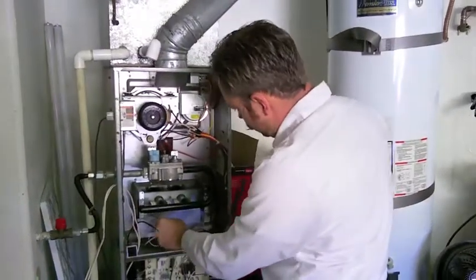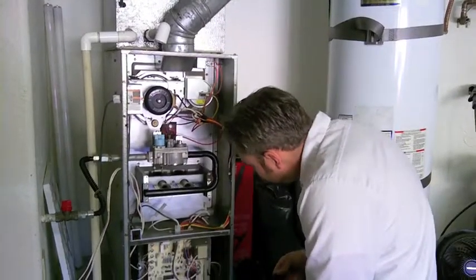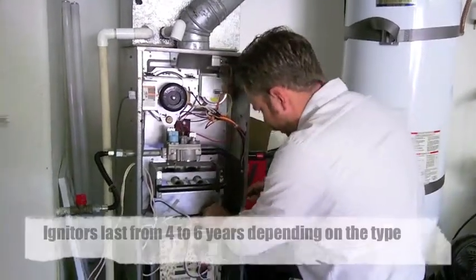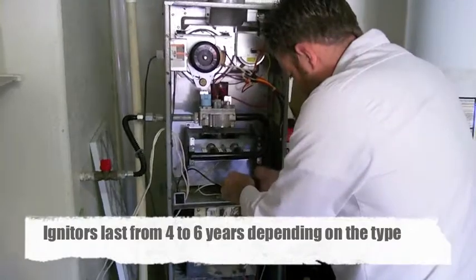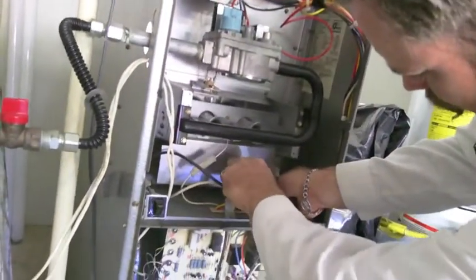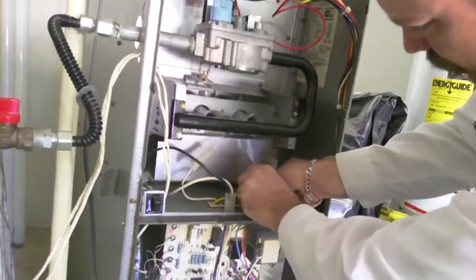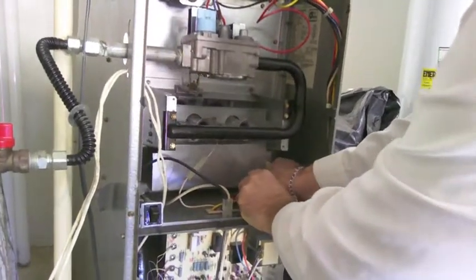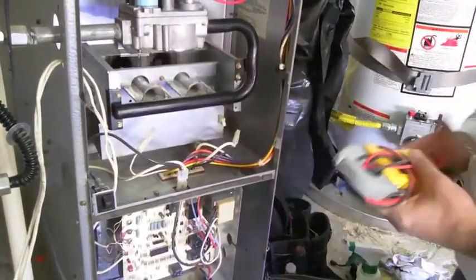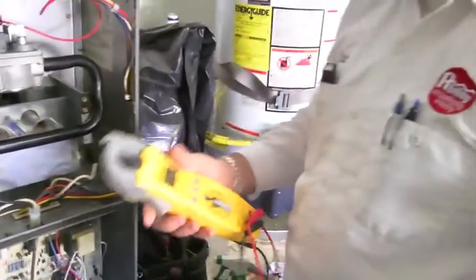The next thing we're going to do is we're going to look at the igniter. And this is what lights up the flame. So what we're going to do is do a resistance test or an ohms test on this igniter.